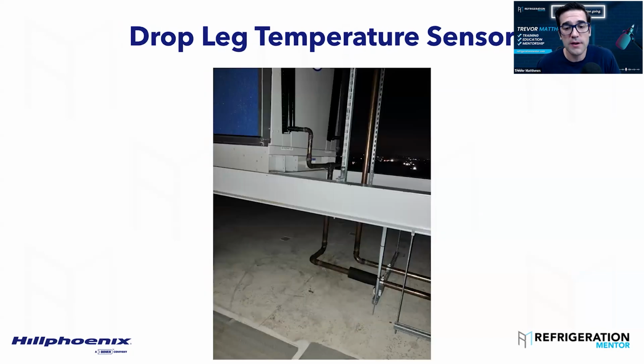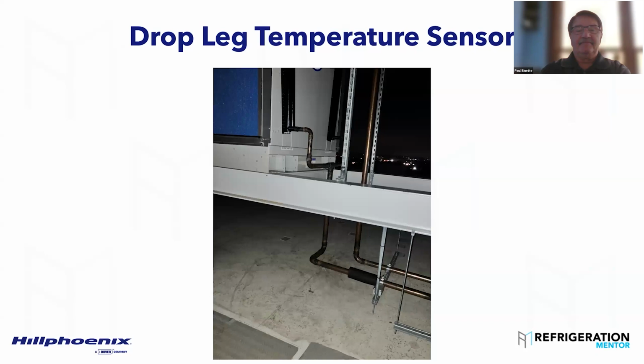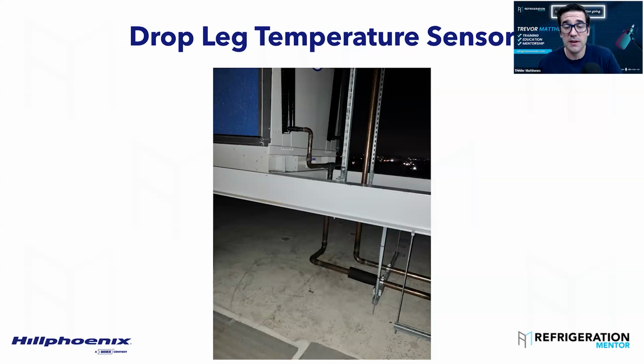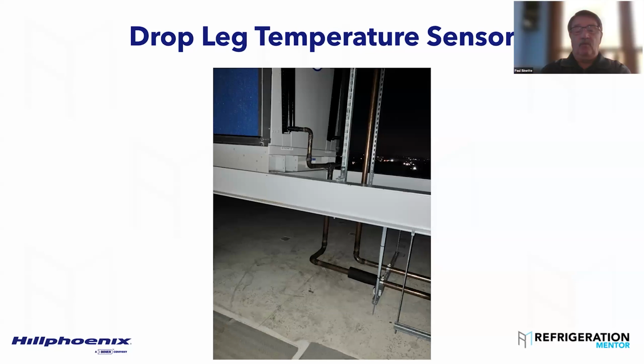This is the most important sensor. This drop leg temperature sensor is the most important, and I've seen it, as well as Paul, probably dozens of times: not in the right location, or not strapped down properly, or not insulated properly, or the wrong sensor, a CPC sensor into a Danfoss controller, or vice versa, not set up properly. Yeah, because once we go supercritical, the HPV, which is reading this sensor, needs to follow a set track of data points that's pre-programmed into the controller. If you get to either side of that because of the temperature difference, you're going to produce too much flash gas. That's more work your compressors have to do, and it takes away from the suction control. Yep.